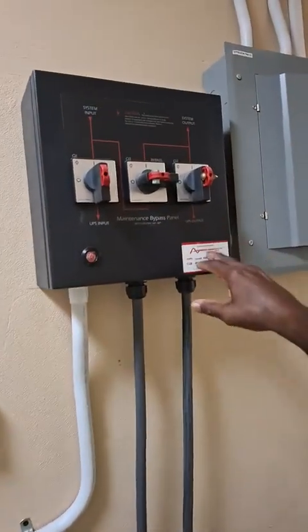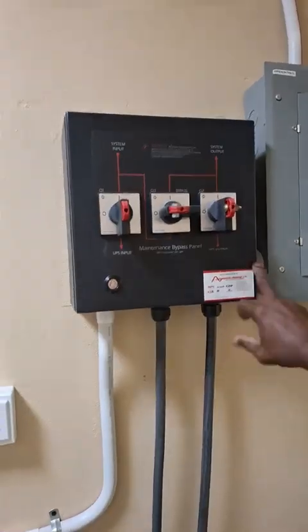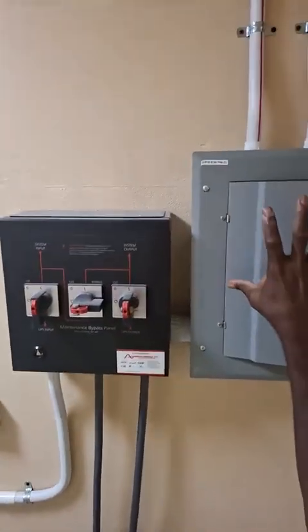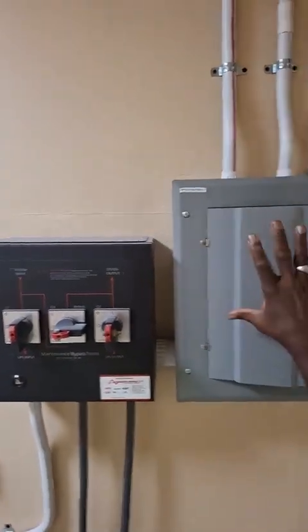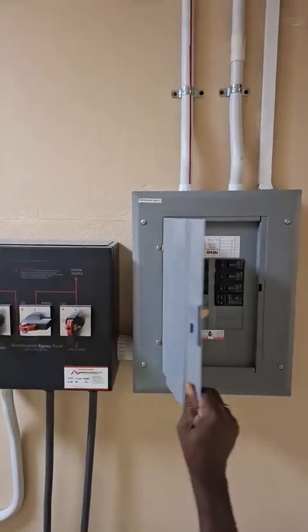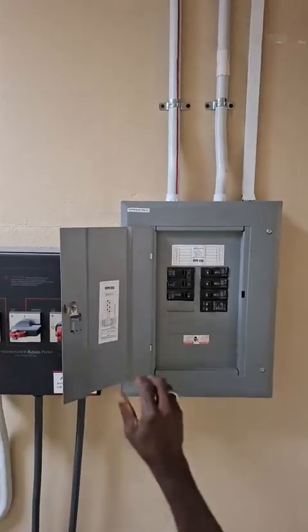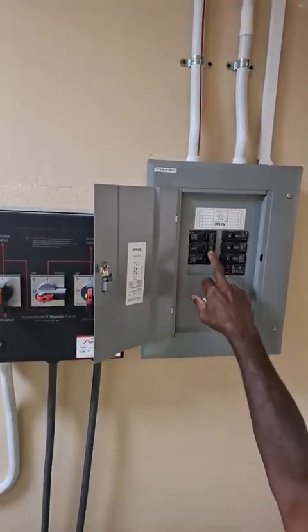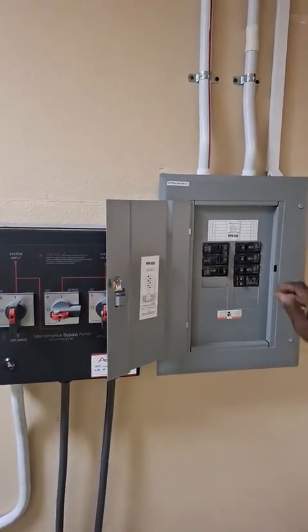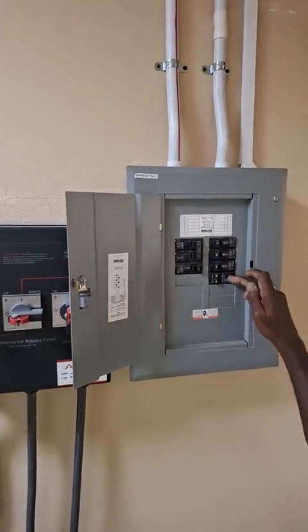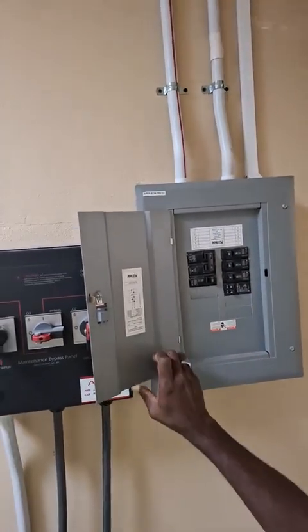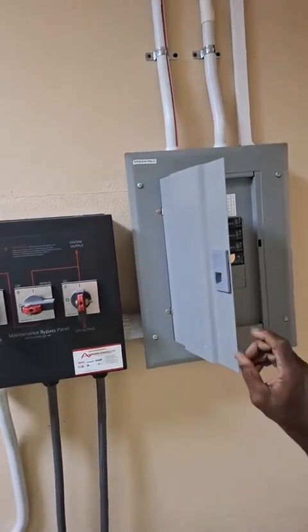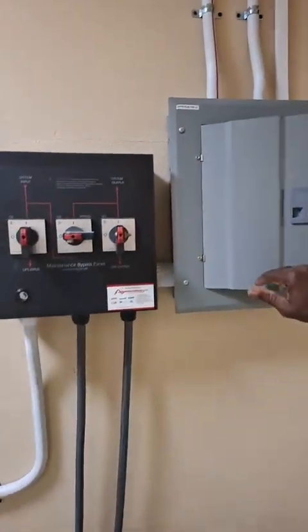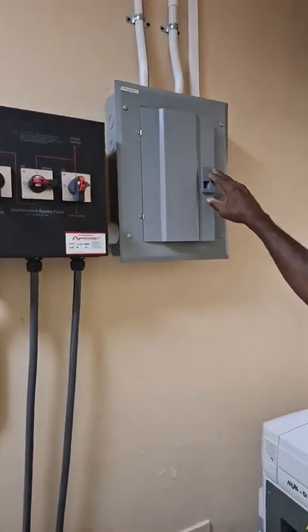And when it comes to that combiner box, it leaves and goes to this 12-way single-phase distribution panel. This panel has a 60 amp double pole breaker, and we have six single pole breakers feeding our UPS outlets.